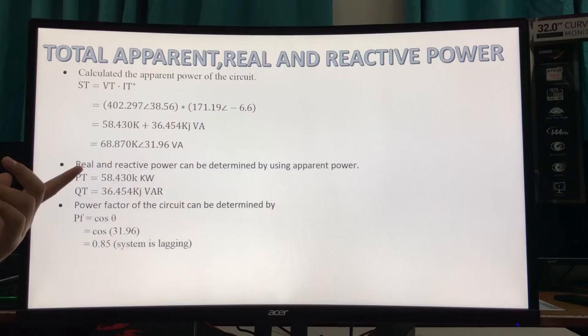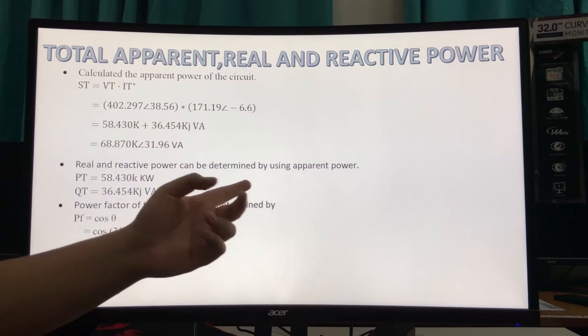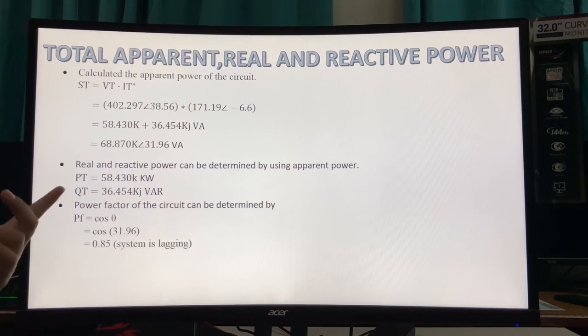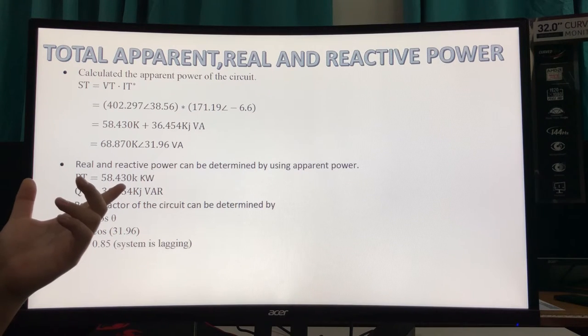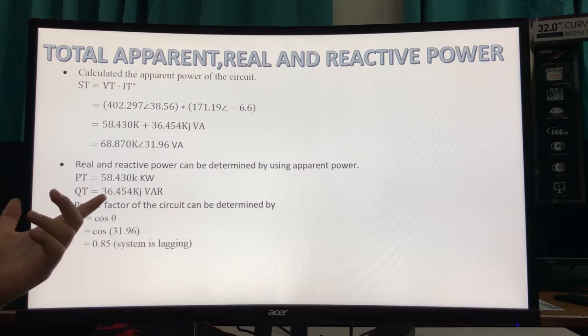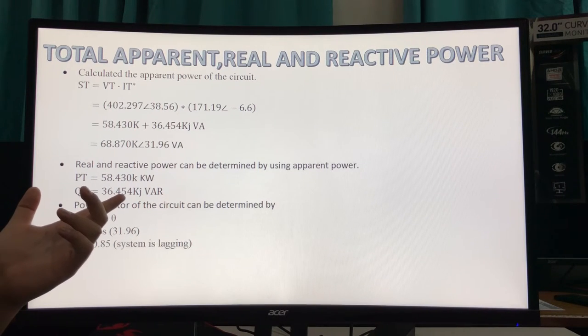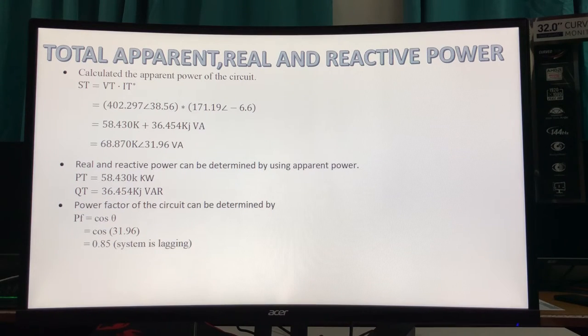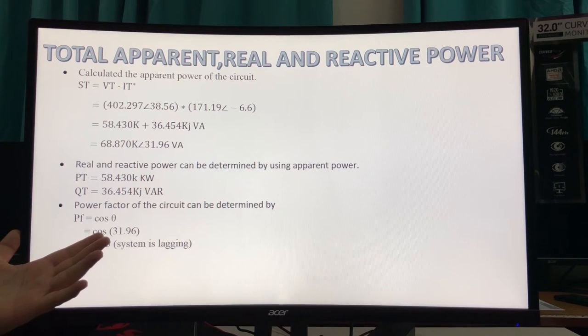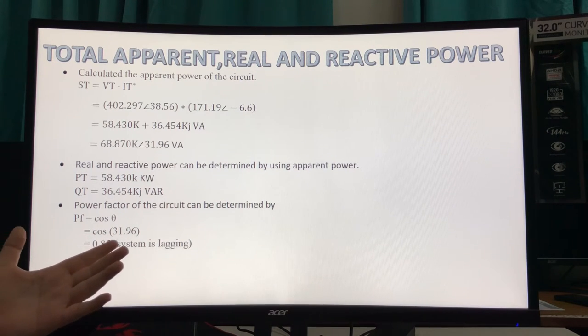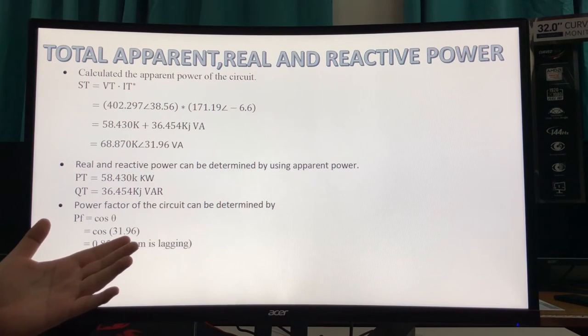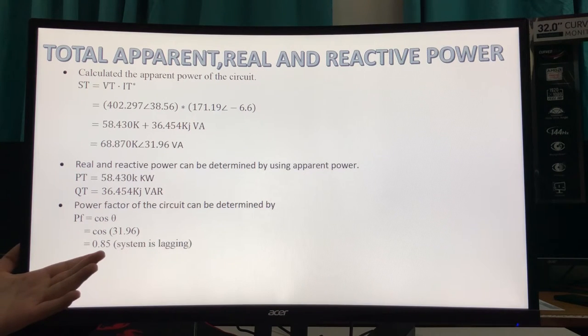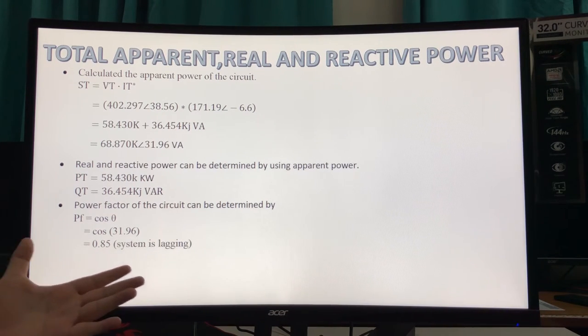Next, we find the real and reactive power determined by using apparent power, which is PT equal to 58.430 kilowatt, QT equal to 36.454 kilo J var. The power factor of the circuit can be determined by power factor equal to cos theta, which is equal to cos 31.96. After we convert it, we get 0.85, which means the system is lagging.